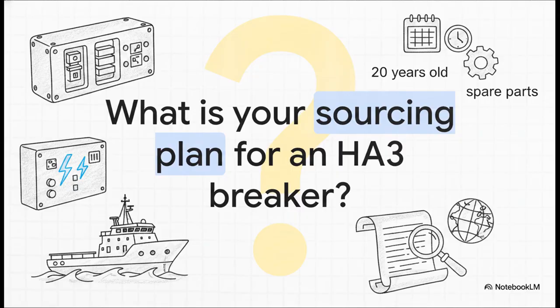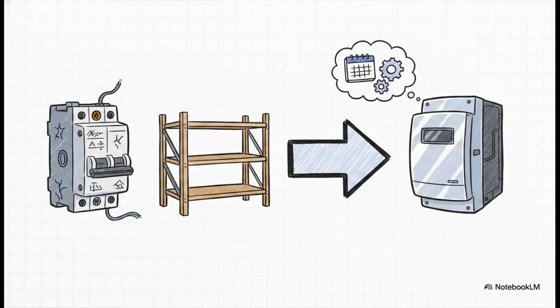Knowing this, let's test how you'd actually apply this hardware knowledge in the field. Imagine you're told to source spare poles for an H3 breaker on a 20-year-old platform supply vessel. What's your realistic sourcing plan here? Well, the stark reality is that you're dealing with a legacy breaker. Since HA3 production has totally ended, you can't just order it off the shelf from the manufacturer anymore. You're going to have to rely on secondary markets or legacy parts channels first. But the real takeaway? You need to immediately start planning and budgeting for an eventual VD4 vacuum retrofit. Never assume you'll have indefinite spare support for discontinued hardware. You've got to plan ahead.